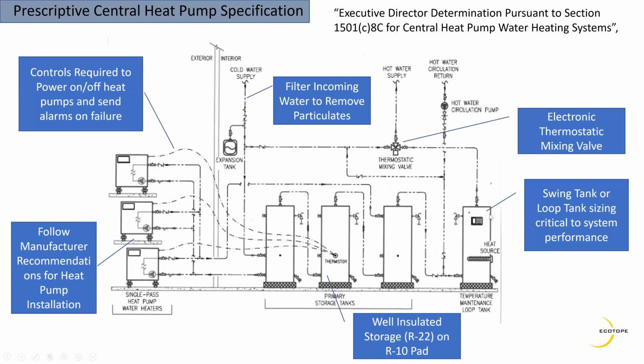We've got a prescriptive sizing, and I'll show you an example of that. But you've got to get the size of that right to be able to extend through the non-draw periods. The storage is really important. So well-insulated storage, R22 and R10 pads on the ground. That keeps our thermal battery well insulated, so we're not losing heat to the outside. The other critical part of this specification is getting the controls required to both power on and off the heat pumps and to send alarms on failure. That's a key requirement with some of these systems.